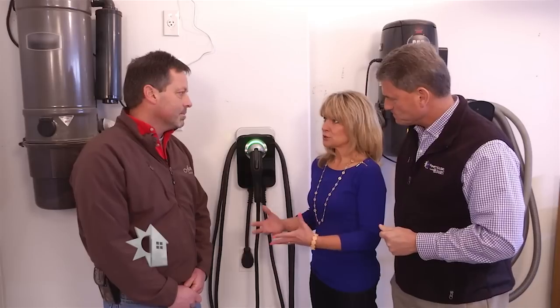Well, like I said, the pre-assessment when you're thinking of buying the car — having an electrical contractor come out. In the assessment, we're going to explain the differences in the chargers and give you an idea of price. The important thing we're going to do is assess your existing electrical panel and make sure you've got enough capacity to take the increased load of a charger. A typical home built in the last 20 to 30 years is usually going to have enough capacity. The older homes with old 100-amp screw-in fuse panels, you're probably going to look at a service upgrade to put a level 2 charger in.